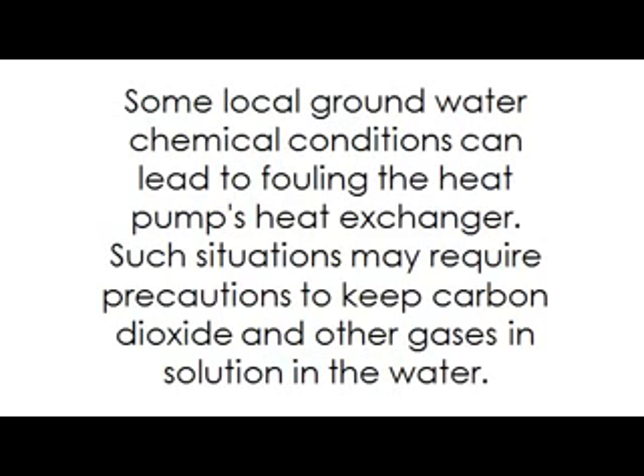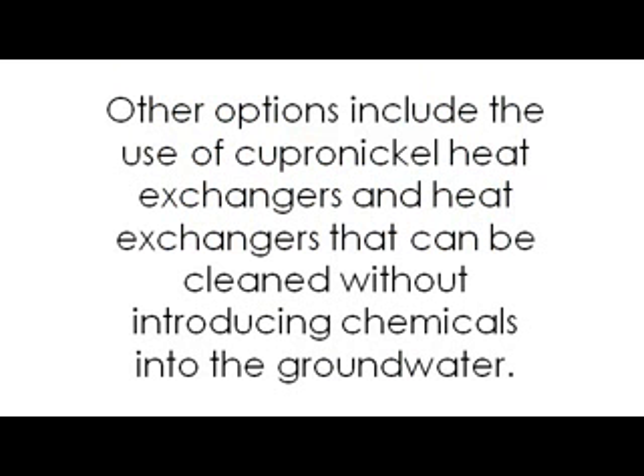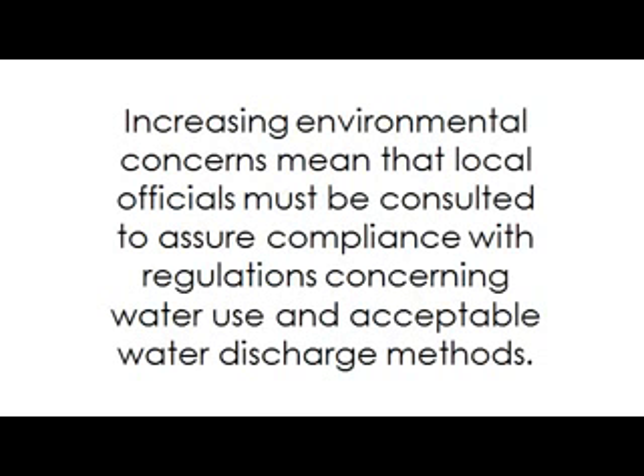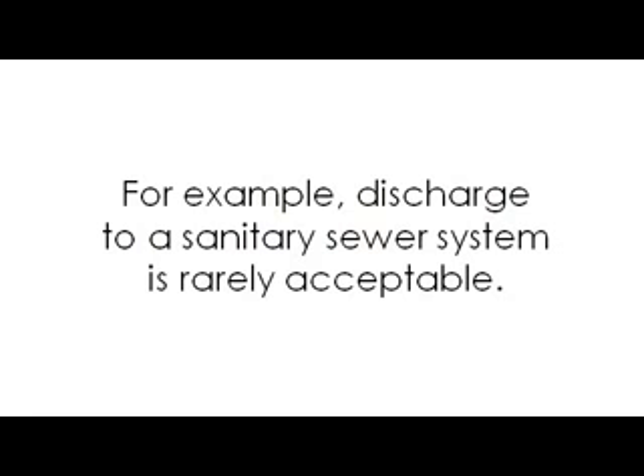Some local groundwater chemical conditions can lead to fouling the heat pump's exchanger. Such situations may require precautions to keep carbon dioxide and other gases in solution in the water. Other options include the use of cupronickel heat exchangers and heat exchangers that can be cleaned without introducing chemicals into the groundwater. Increasing environmental concerns mean that local officials must be consulted to assure compliance with regulations concerning water use and acceptable water discharge methods. For example, discharge to a sanitary sewer system is rarely acceptable.